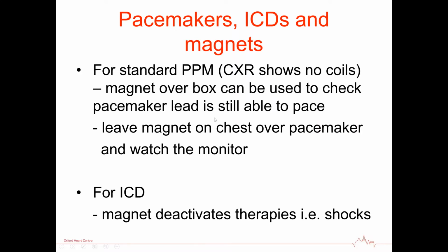If you put a magnet over the box, and there are magnets in almost all defibs and all EDs, the little blue round ones normally look like a donut, and you have to leave it over the box. What it does is it flicks a reed switch within the pacemaker, and it reprograms it to the manufacturer's baseline rate. And it's still like a BMW, a Volkswagen, a Ford. They've all got their own preset rate.